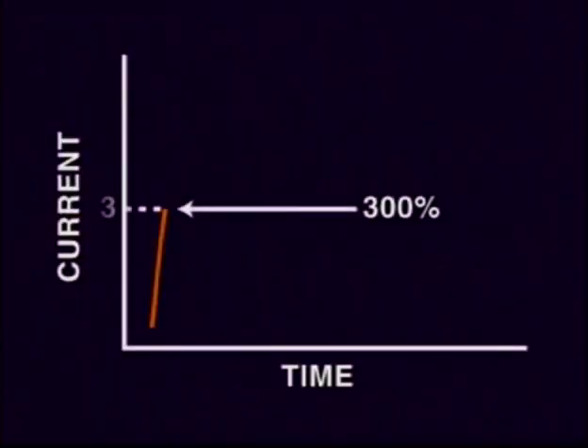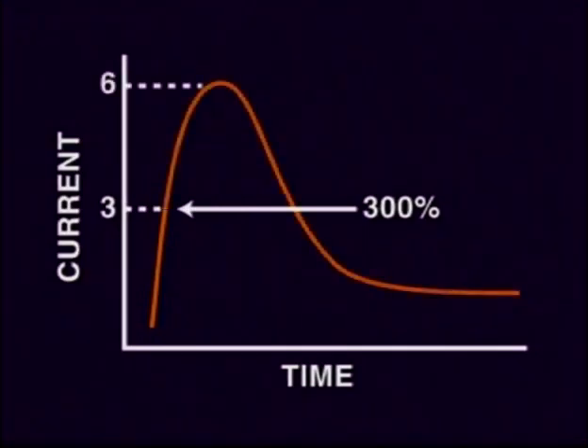When we talk about the National Electric Code, non-time delay and dual-element time delay fuses are rated under normal conditions in the range of 300 and 175% of the full load current of motors. This gives, for example, a non-delay time fuse only 3 times its rating to allow for the start of a motor. And we know that a motor may take at least 6 times the full load current when it is first started. The reason is that fuses do not open instantly at a current just above the fuse rating.